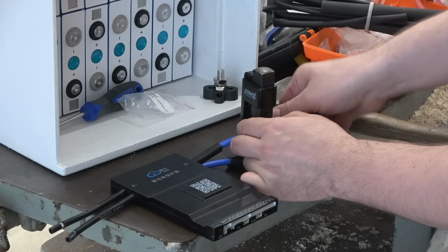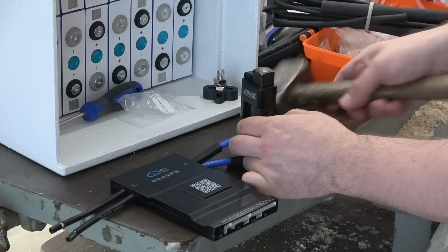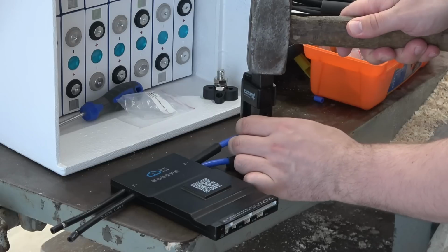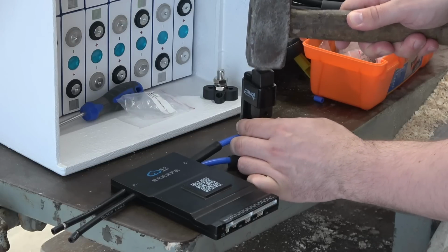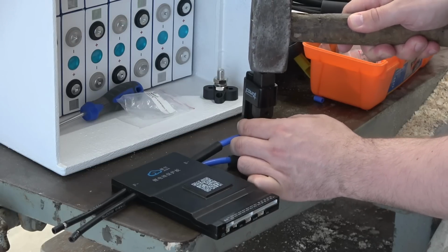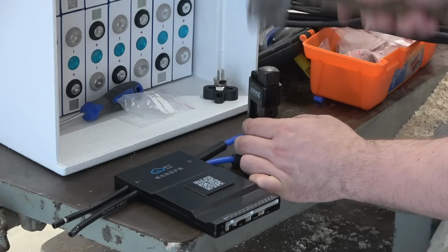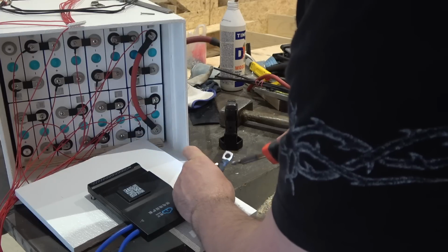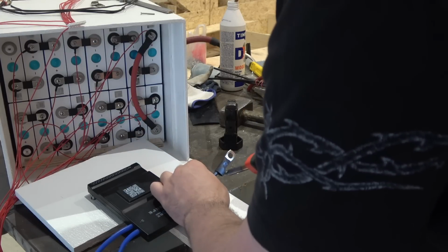The 20 square millimeter lug was slightly too small, and the 25 square millimeter, the next size up, was a bit too large. But I used the larger ones, and with the wire whacking press connection tool it came out perfect. Then some heat shrink on them, and they were done.